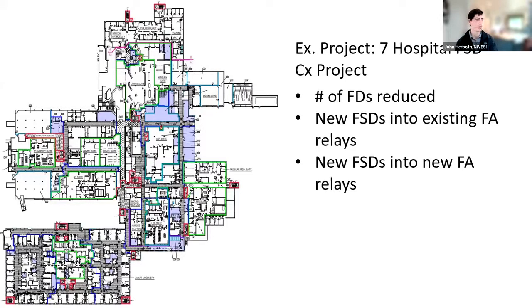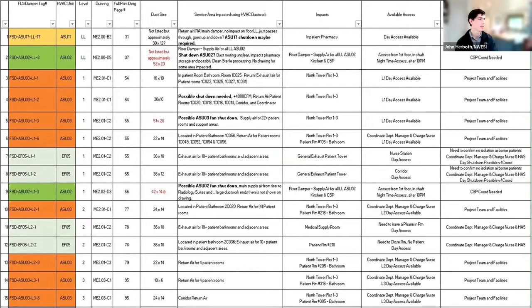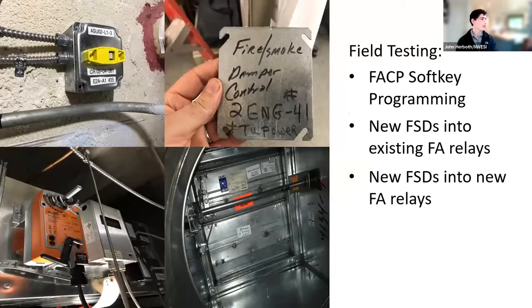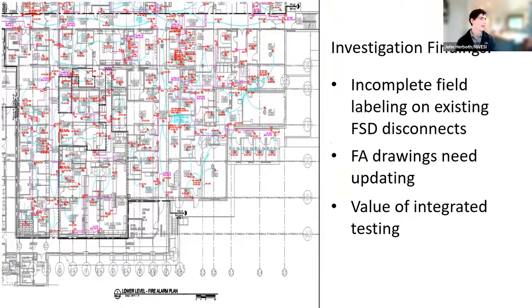New building, obviously you could do it completely. An old building, you run into situations where you really need to track down, and that spreadsheet gets huge for who you're going to impact, what rooms you're going to impact. You have to trace ductwork in the drawings, whether it can be done during the day, night, you name it. It ends up being a huge coordination effort, and your typical contract could easily exceed $50,000, $100,000. Try to get those relays with switches in the field, get stuff labeled. Great. Update fire alarm drawings if you can with where the relays are located. Typically it's outside of the electrical room.